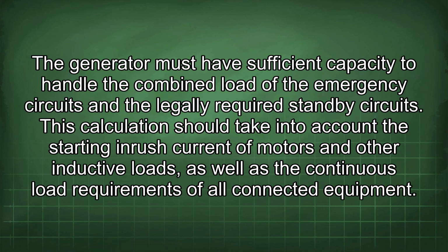The generator must have sufficient capacity to handle the combined load of the emergency circuits and the legally required standby circuits. This calculation should take into account the starting inrush current of motors and other inductive loads, as well as the continuous load requirements of all connected equipment.